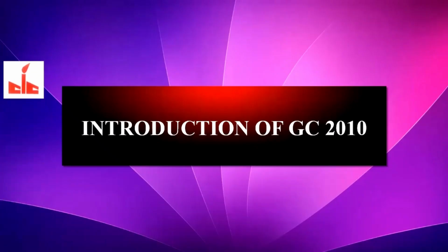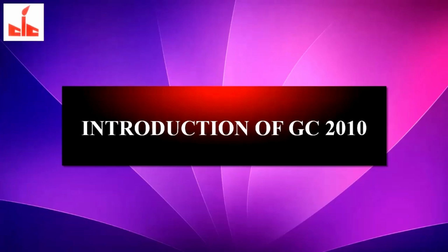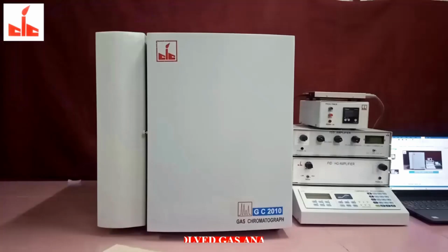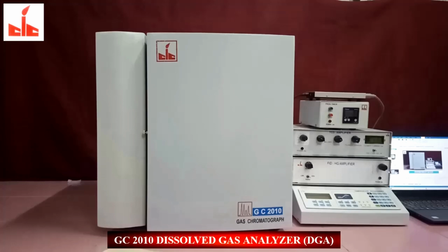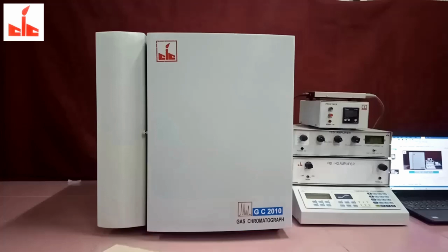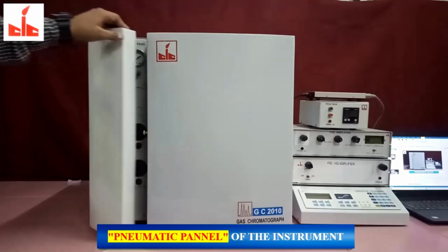Introduction of GC 2010. This is the complete setup of GC 2010. This instrument is configured as a dissolved gas analyzer. It is also called DGA. DGA is used for the analysis of gases dissolved in transformer oil, and to prevent sudden breakdown of the transformer. This is the pneumatic panel of the instrument.